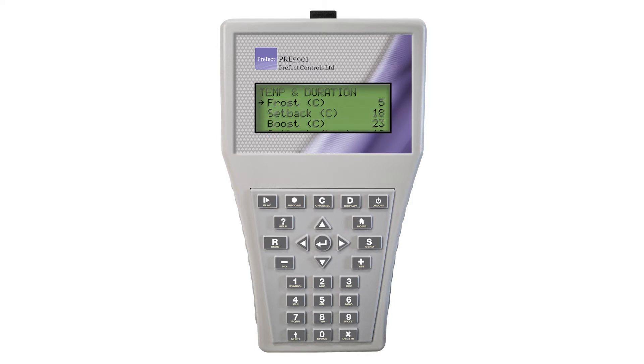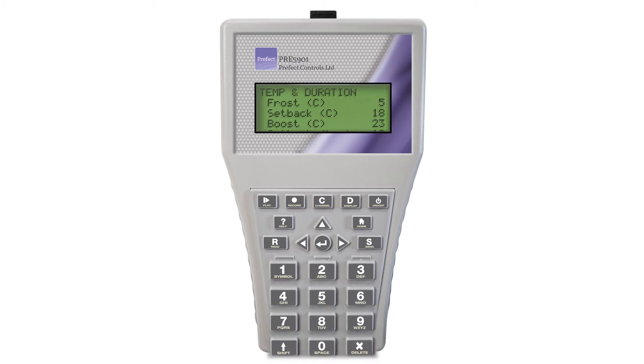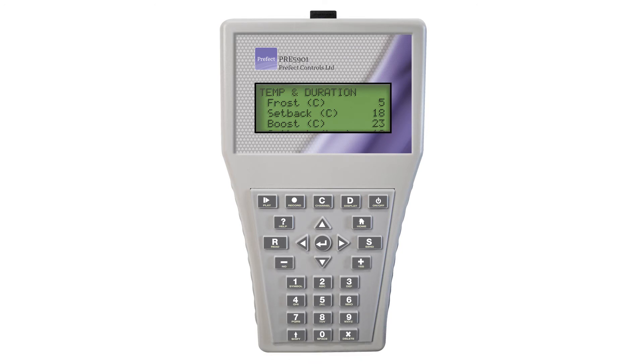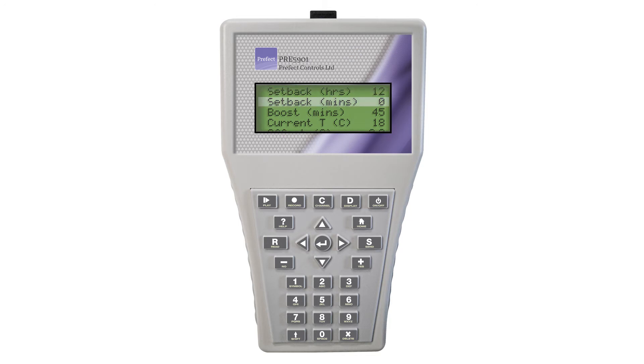The arrow on the left denotes which item is currently selected. To change the temperature value for each of these modes, press the plus or minus buttons. You can also input a number directly using the numerical keypad. Now scroll down to the time settings. For setback, you can choose hours or minutes — this is the length of time the thermostat will remain at setback temperature before activating frost mode. Use the plus and minus buttons to change the values. For complete hours, just use the hour segment; for minutes, use the minute segment. For a combination such as 1 hour 30 minutes, set the hours to 1 and the minutes to 30.